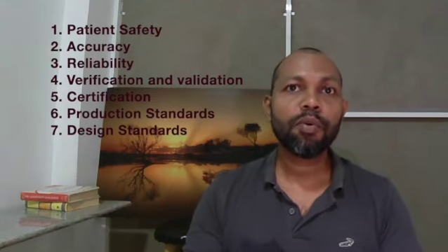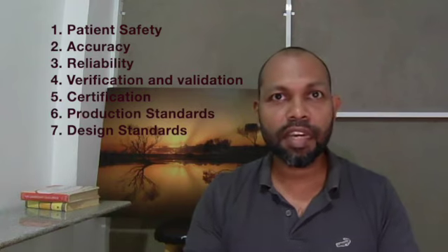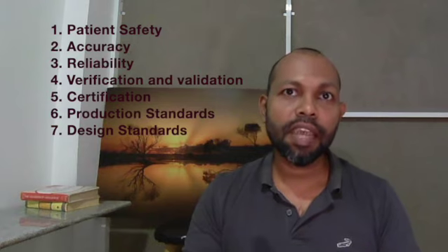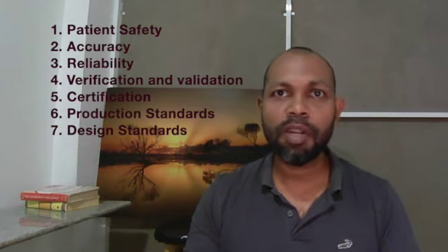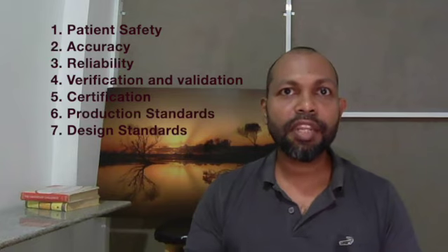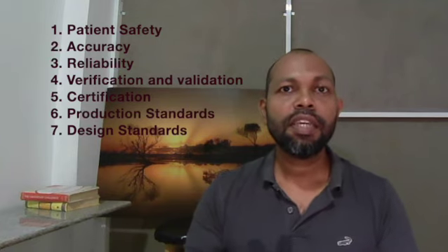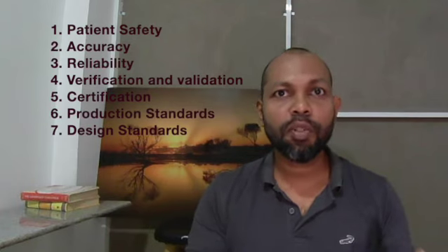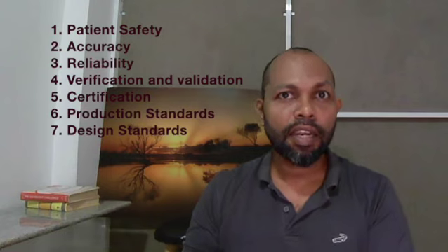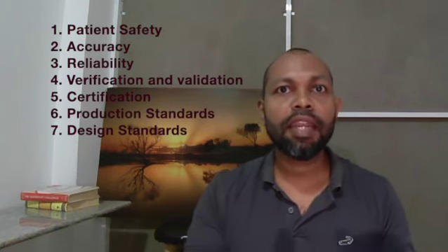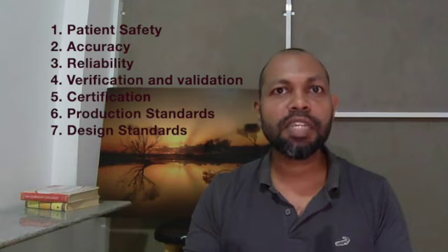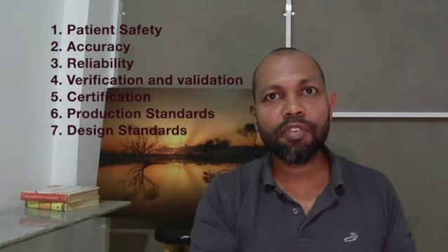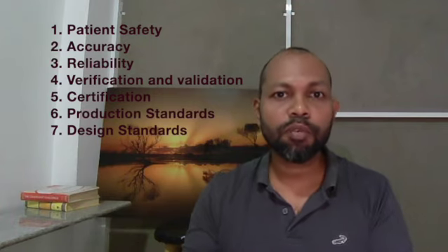And then after all the certification is done and everything is approved, you have to make sure that production is done according to the given production standards. Normally it's ISO 13485, but there are a lot more that you have to adhere to when you are producing the medical product. Those standards are given to make sure that all the products that you are producing are 100% tested and reliable, and those components and production procedures are done according to a given standard, so that even in bulk after 10 years you have the exact same quality product as your output.